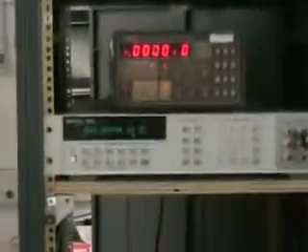All the mixture comes back to the dump, and the temperature goes up, and the system warmed up. But we also need to be a little bit careful about this instrument rack, because after a power shutdown, a lot of the equipment will reset themselves. So we need to be sure that it's in the correct state.